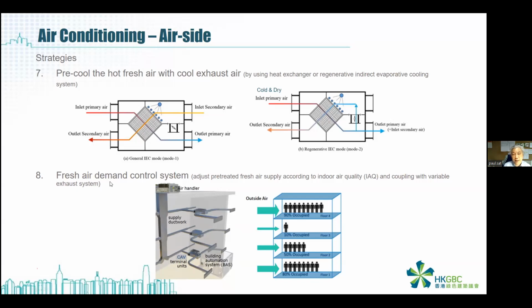temperature. Okay, here you can see the primary air, or the fresh air, passing through a thermal wheel and then going out. The return air also passes through the thermal wheel and then goes out. But before they pass through the thermal wheel, they use water to do evaporative cooling for the return air, and use this cooled return air to cool the intake of the fresh air, so this is more effective than the thermal wheel.